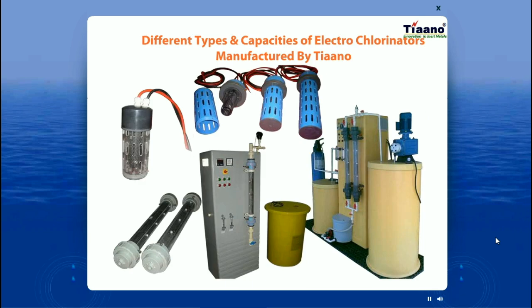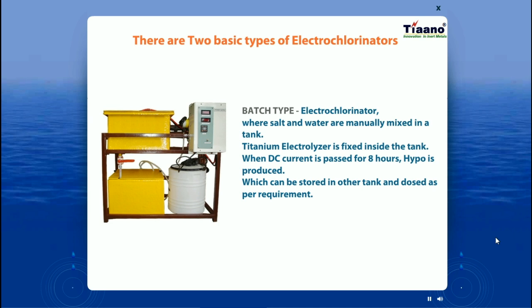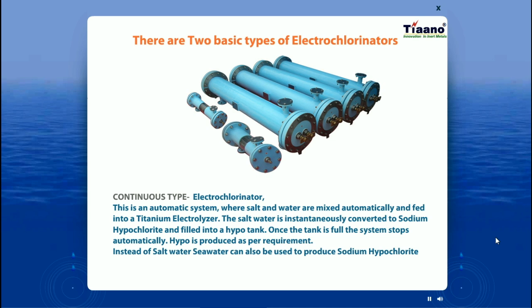There are two basic types of electrochlorinators. The first is the batch type: a measured quantity of salt and water are mixed in a tank with a titanium electrolyzer. DC current from a rectifier controller converts the salt water into sodium hypochlorite over eight hours, with an electronic timer shutting off after producing the required amount. The second, more advanced type is a continuous production system where salt and water are mixed automatically, fed into a titanium electrolyzer, and converted instantly to sodium hypochlorite. Seawater can also be used directly instead of salt water.